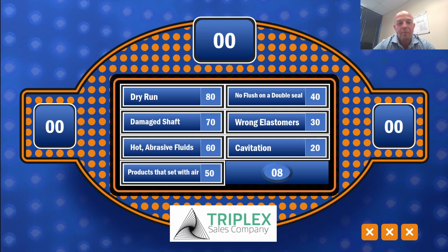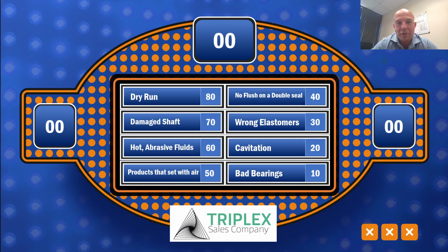We just touched on it. Our last reason for premature pump failure: bad bearings. When our bearings are loose, and we can check this, it is one of the first things we check when we go to evaluate a pump. We did a post on this, how to evaluate a Waukesha PD pump for repair in about 5 minutes. Basically, you want to pull the pump off, and even before you pull the body off, you can turn the shaft. It should turn.